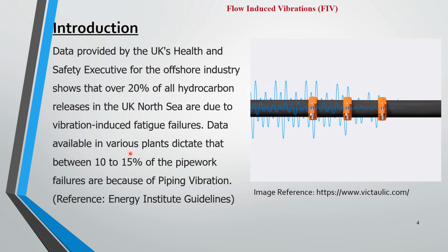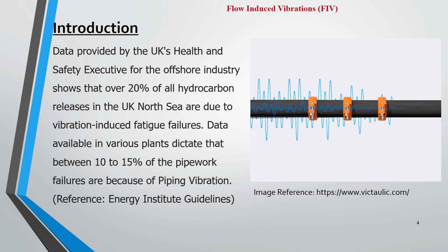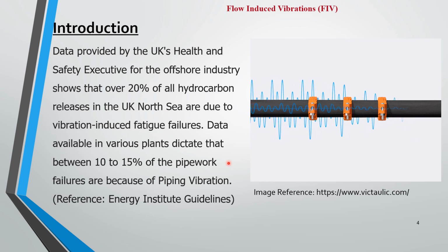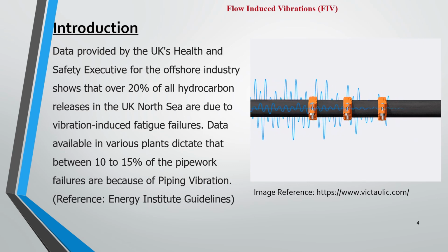Data available from various plants shows that between 10 to 15%, a major chunk of pipework failures, are because of piping vibration. This is the reference from the Energy Institute guidelines, based on which we usually perform our FIV study or flow-induced vibration studies.